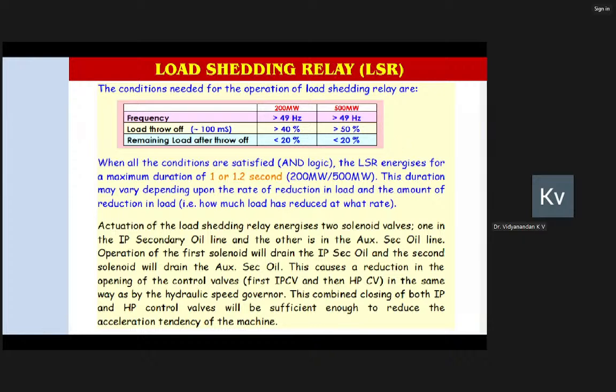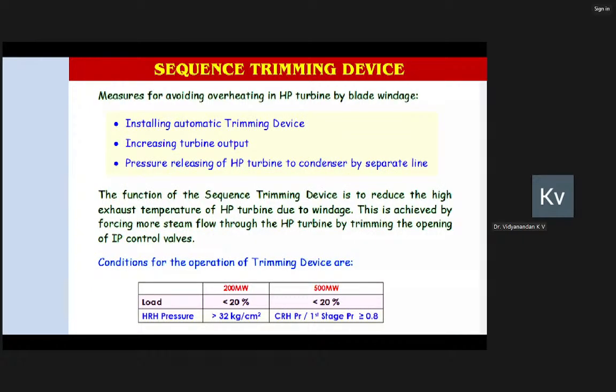Similarly, there is one more device, the so-called sequence trimming device, or simply trimming device. Under certain low load conditions, there is a possibility of your HP turbine getting starved. Those from an O&M background must have noticed that even when your unit is running at full rated load, your HP control valve opening will be much less, whereas IP control valves will be 100% open. So if there is a sudden reduction in electrical output, that will result in further closing of the HP control valve opening. In that case, there is a possibility of the HP turbine getting starved, and that will result in very high temperature build-up in the turbine blade chamber area, and your blades may get affected.